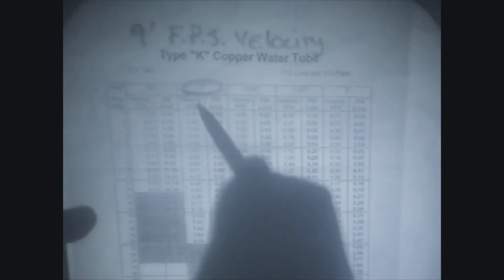On the copper chart, you'll notice we have the different sizes of copper across the top. And we had said 1-inch copper is a service on this design. The rule of thumb on this copper chart is not to exceed 9 feet per second velocity. So on our 1-inch copper, here's our velocity column.